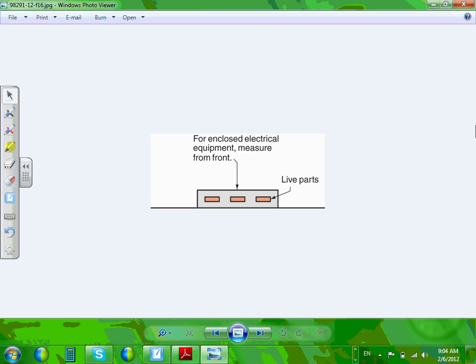Measurement, it doesn't bother us, guys. We always measure the 3 feet dead front from right here, the cover, 3 feet in. The electrical industry is a big industry, guys. If this panel is open, can I have a panel that's open? Yeah, in certain applications, in a vault. If its bus is open, no cover on it, you can. They have it in vaults. Then you measure from the hot bars. There is no panel, nothing enclosing it. For you guys, probably 99% of you will work in panels that have a cover, so you measure from the cover. That's what they're trying to do here. If you have a cover, you measure from the cover.